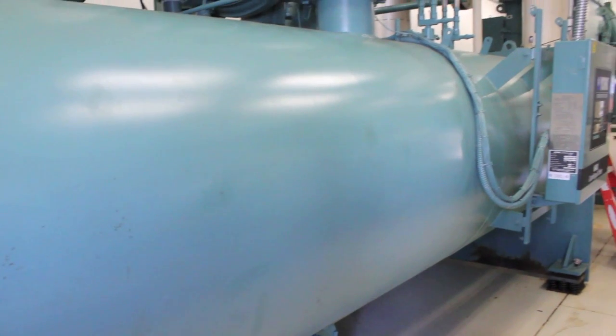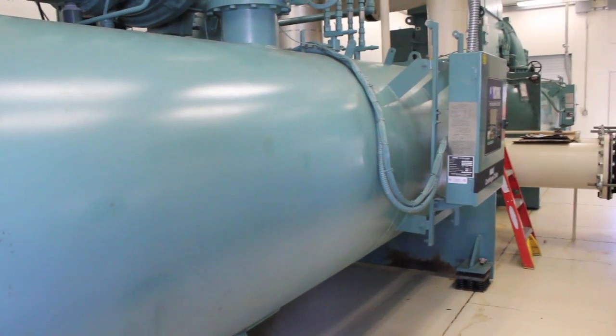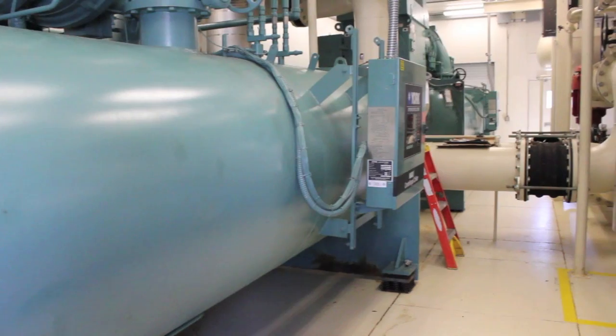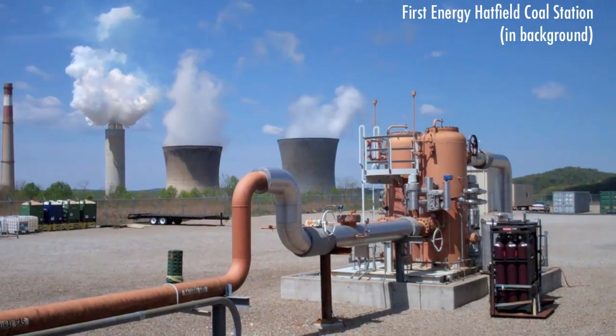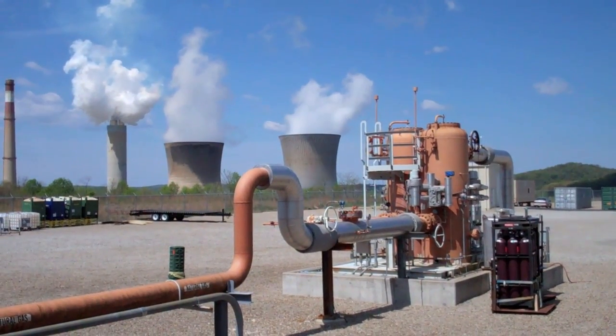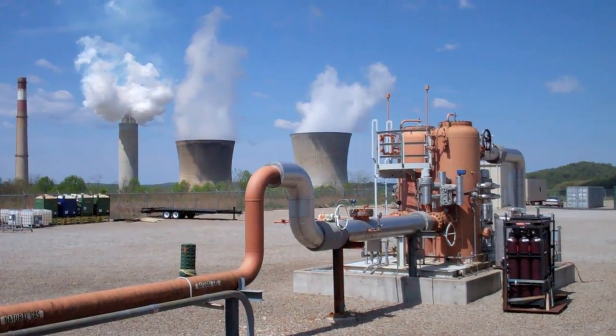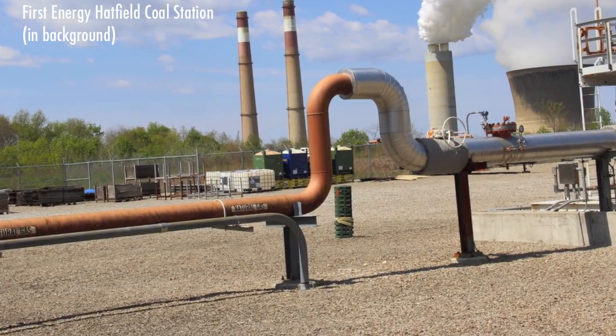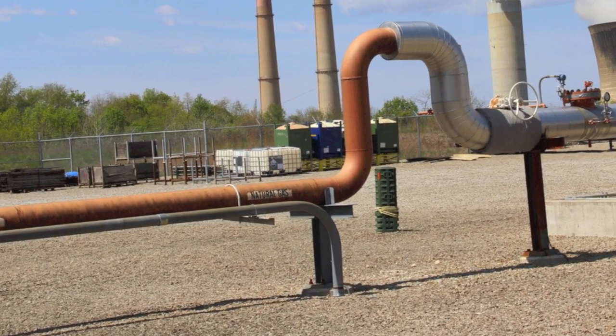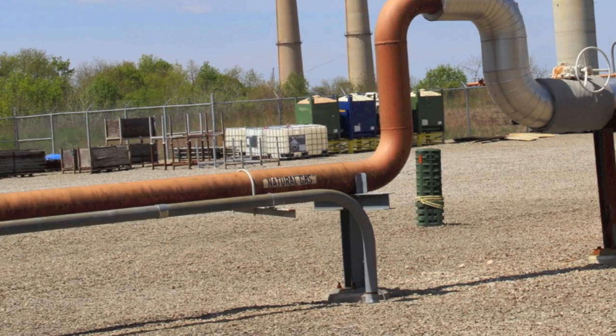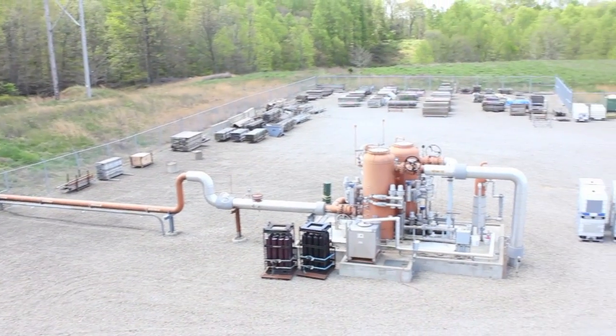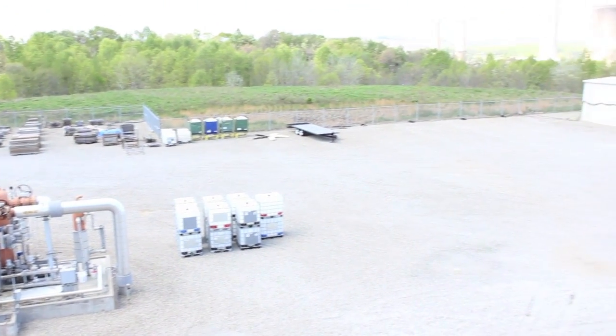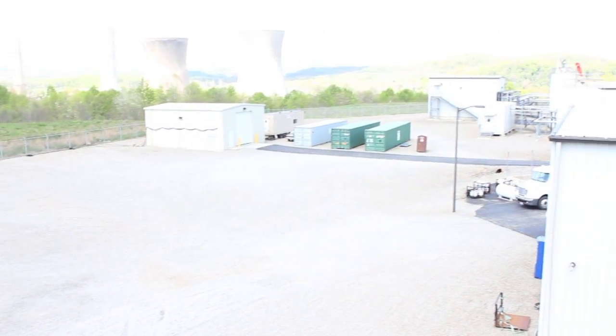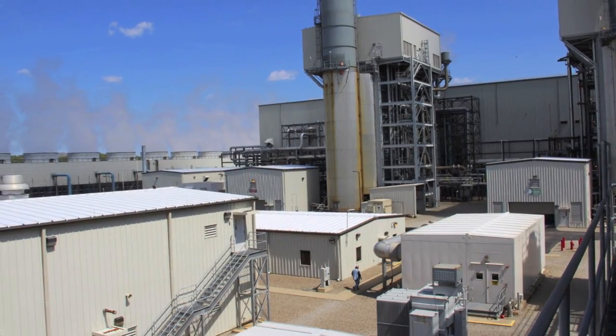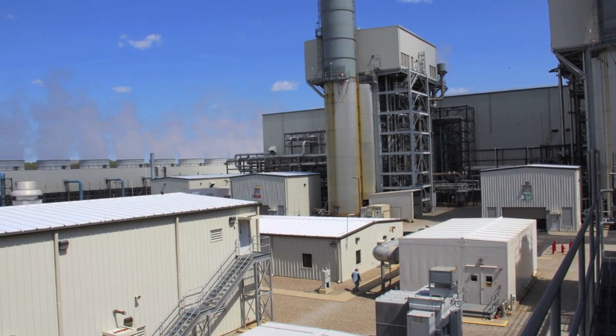They have massive air conditioning compressors on the inside, as well as a condenser on top of each unit for cooling. This is where the fuel gas comes into our facility. We get our gas from Spectra Energy. They're a natural gas provider for us. It comes through the moisture separators that you see, and from there it goes underground and splits out to all the different places in the plant that we use natural gas, including the gas turbines, the building heat, the duct burners, and all of those things.